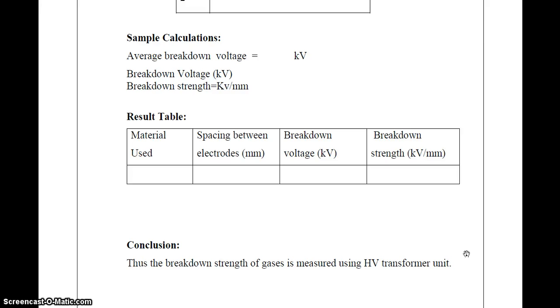Then the breakdown voltage concept. It is also called striking voltage, the voltage at which electrical insulation ruptures, thereby destroying its insulating value and permitting current flow. It is measured in kilovolt per mm. This concept is very important in the design of electrical equipment. It gives the maximum voltage that can be applied to the equipment. Breakdown voltage is the characteristic of an insulator that defines the maximum voltage difference that can be applied across the material before the insulator collapses and conducts. This concept is called breakdown voltage.